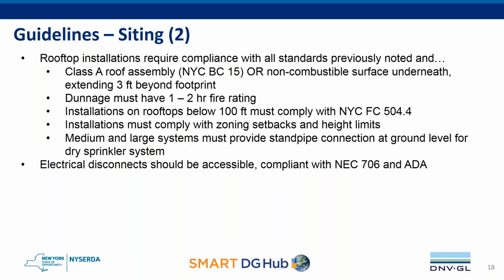If the unit is installed on dunnage, that dunnage must have a 1 to 2 hour fire rated coating on it. For installations on rooftops below 100 feet, they must comply with New York City Fire Code 504.4. That's related to access on the rooftop. Otherwise, the installations have to comply with zoning setbacks and height limits.